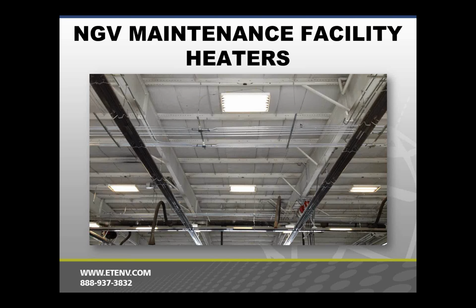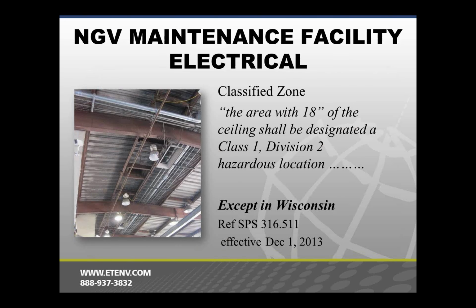Electrical is the next one. Normally, everywhere that I'm aware of, except for Wisconsin, has this classified area at the ceiling. In Wisconsin, passed in December of last year, they made a code revision that says if you have the ventilation, as we just talked about, that's compliant for NGV garages, then you've eliminated your classified area at the ceiling, which is a huge cost savings. And my hat's off to Wisconsin for making that revision.